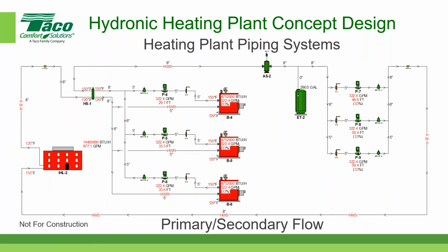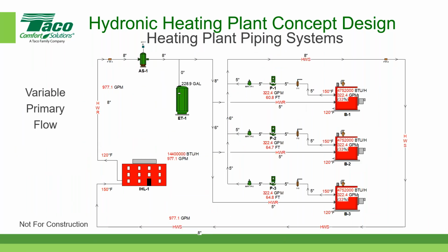All right, so this next one. How did you come up with 977.1 GPM? I think it was just the software coming up with that, right? Or I don't even see it. Oh, there it is. It's over by the air separator. Oh, by the imposed load. Yeah, well, in this case, it's a 30-degree differential temperature. If you remember, the total load in the building was 14,400,000.